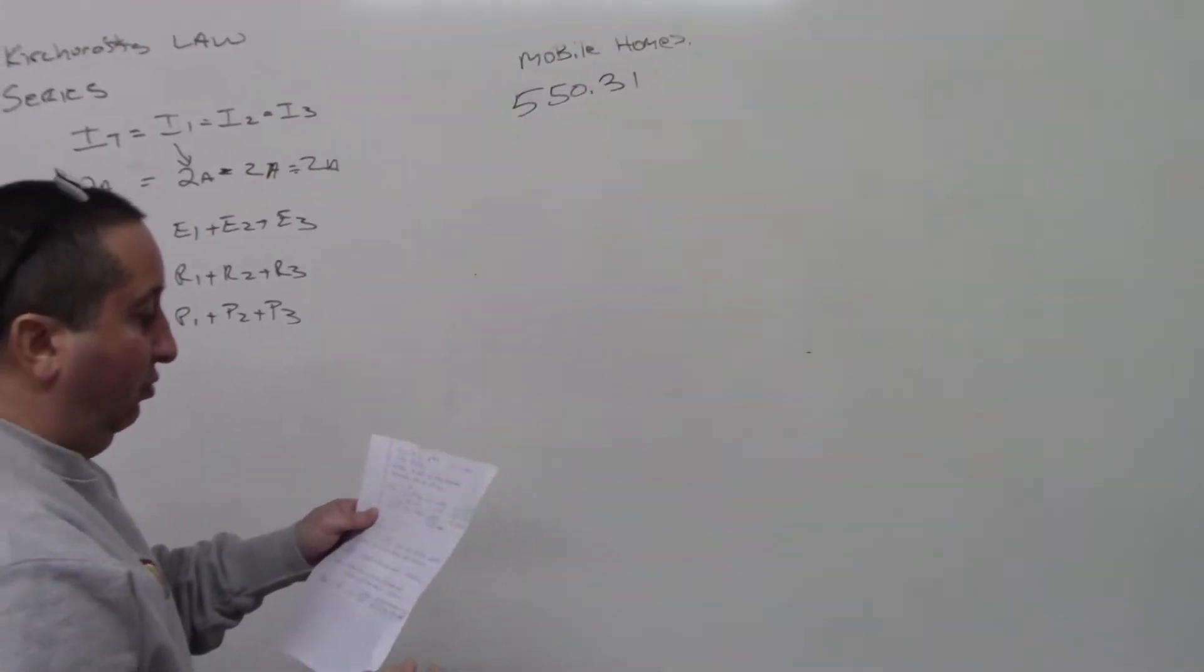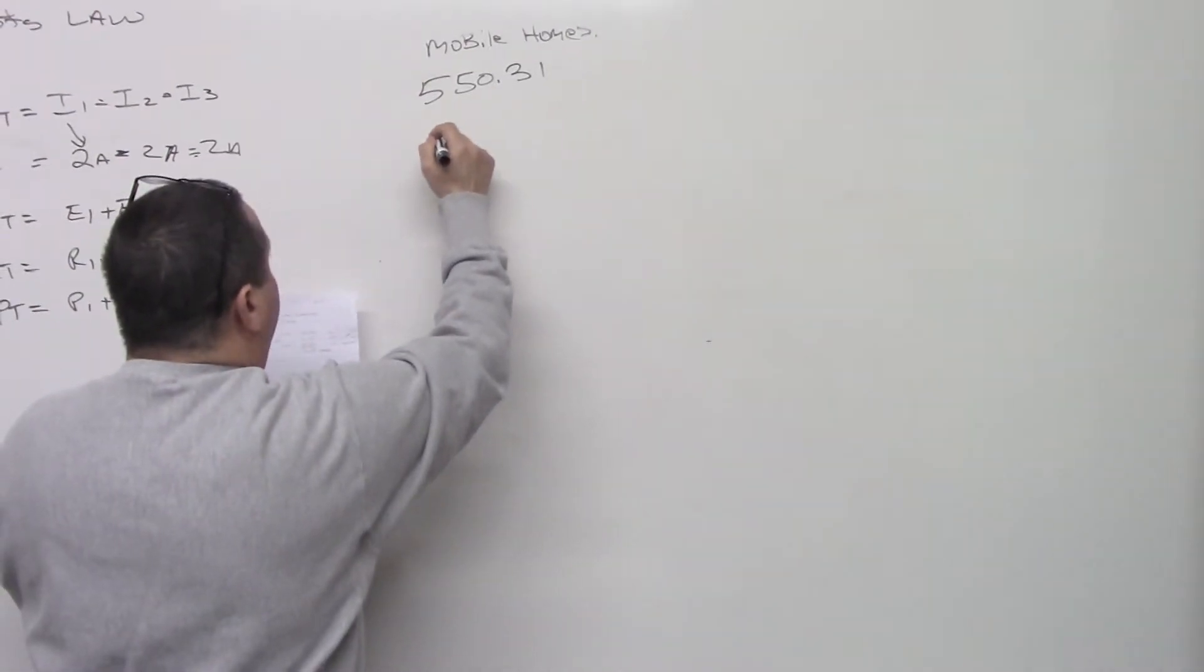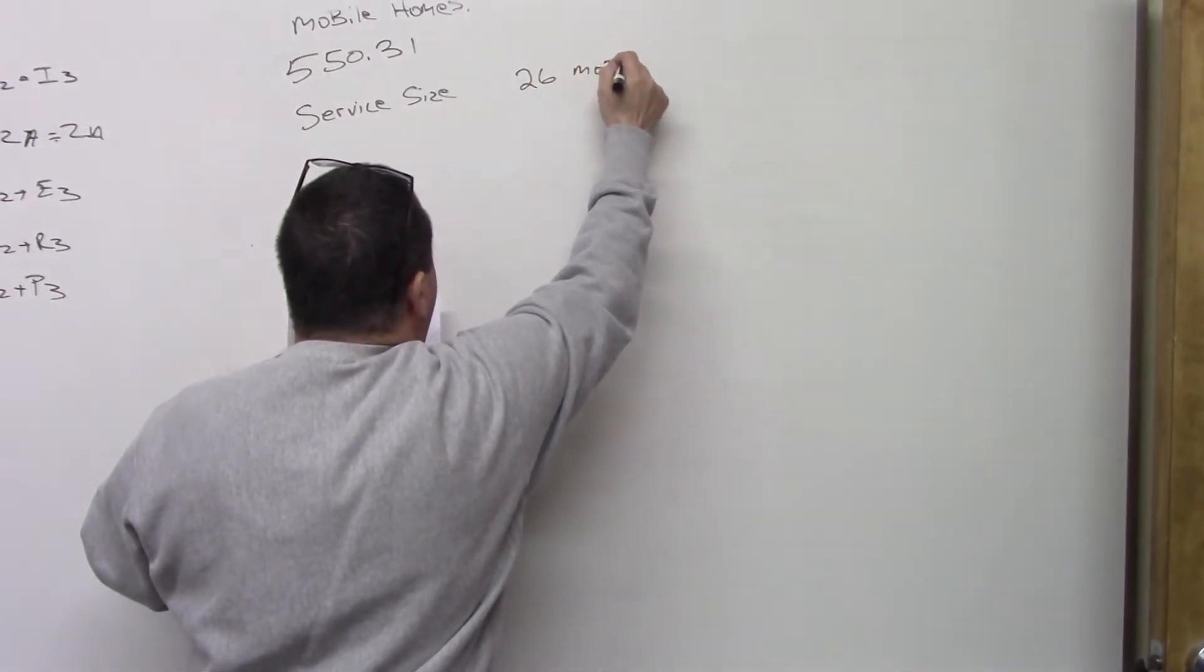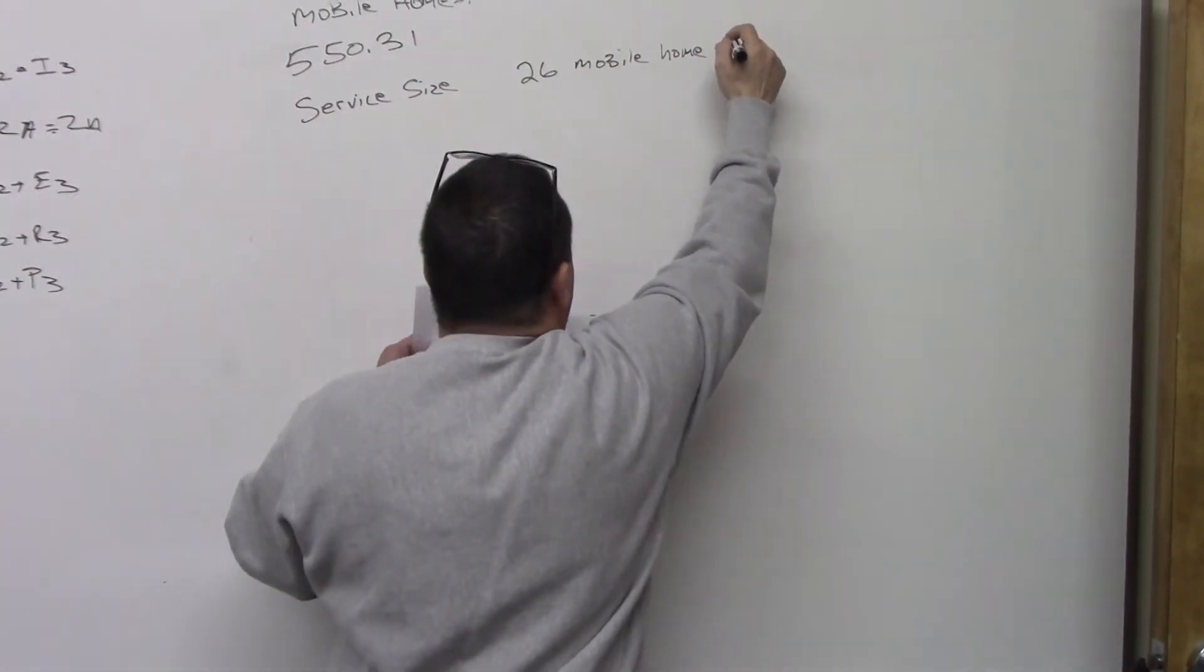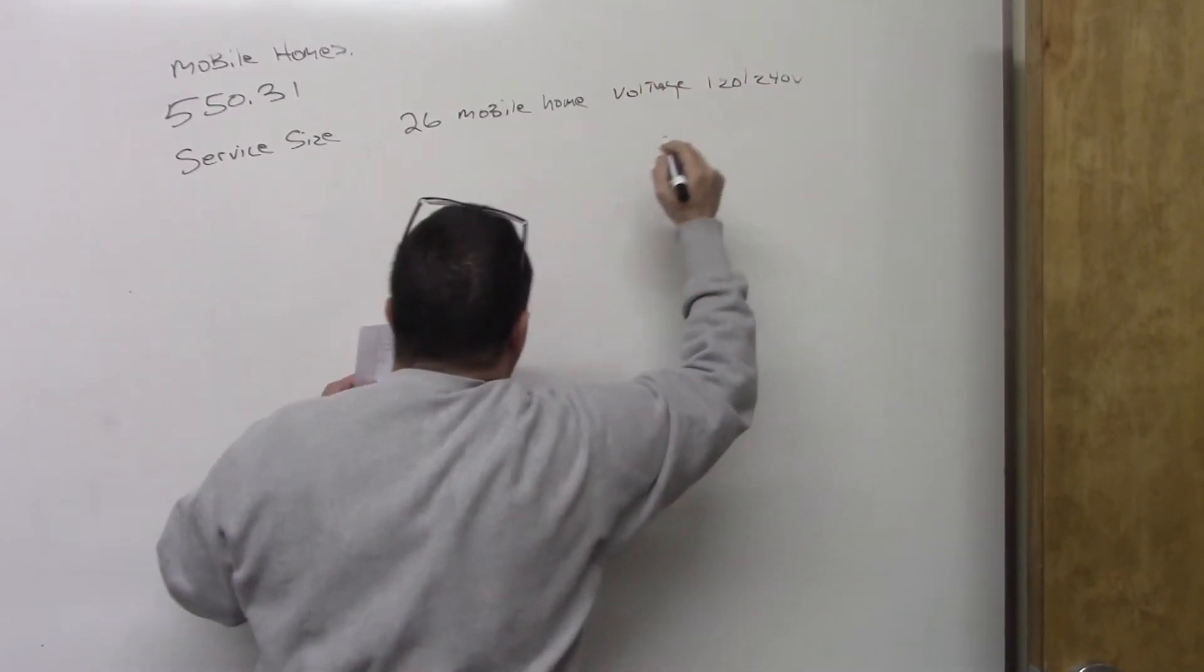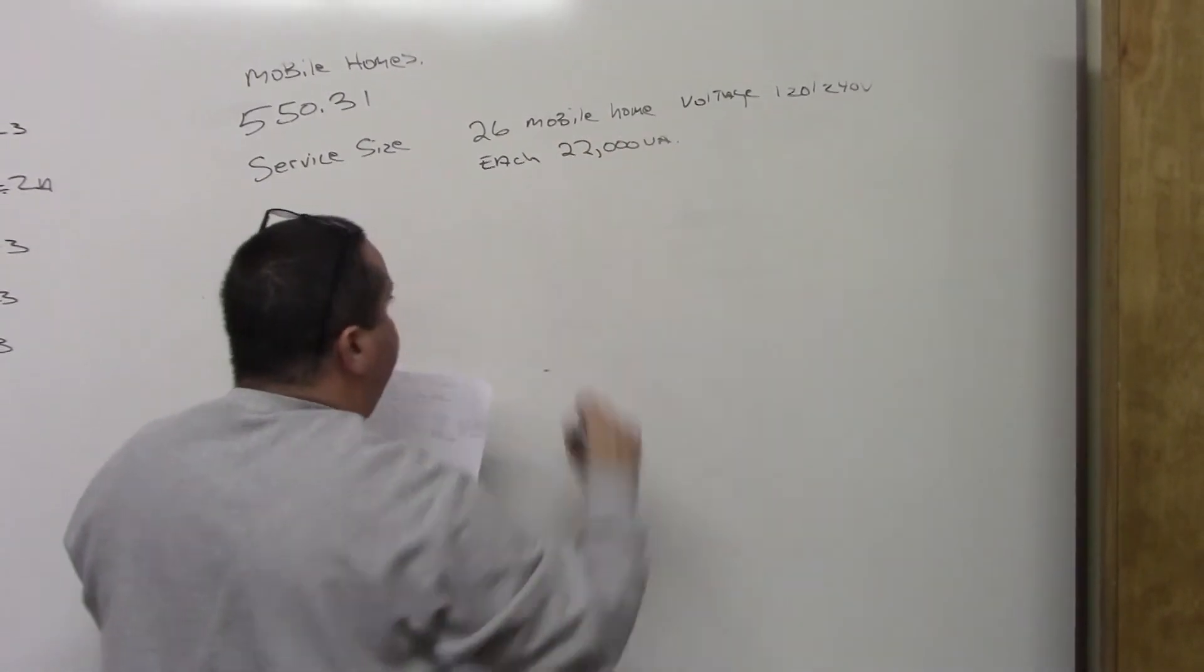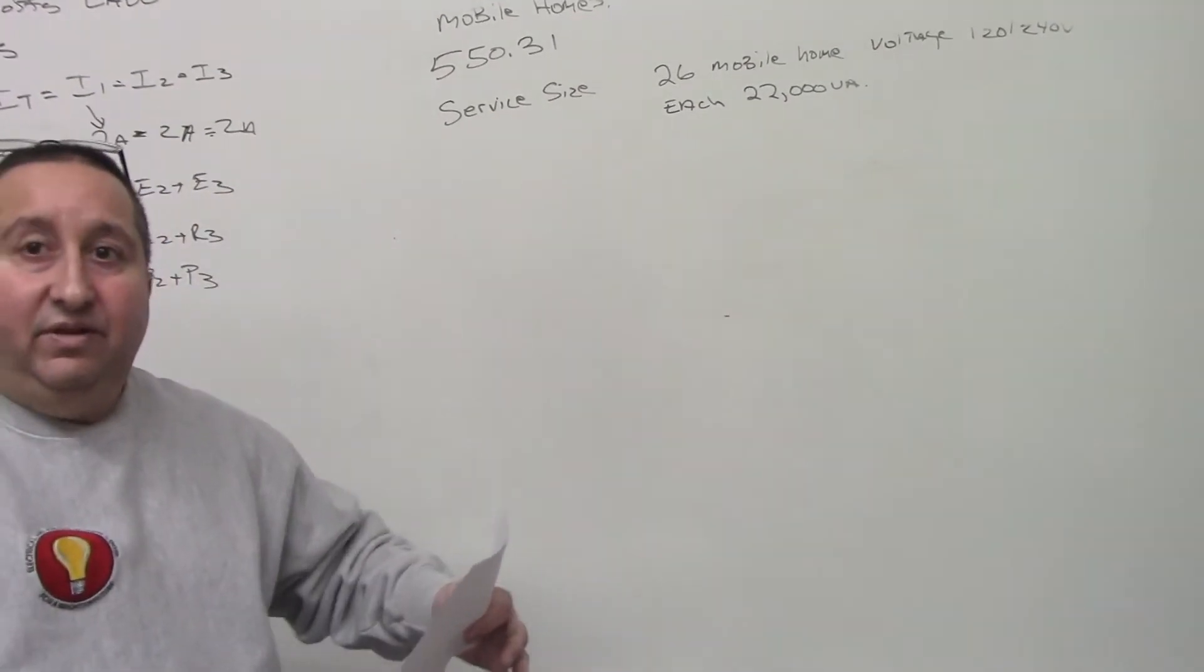So let me explain what is given and what the problem is. We want to know what the service size is for 26 mobile homes. And the voltage for this is 120/240 volts. And each home, we have a calculated load of 22,000 volt amps. So we want to find out the service conductors, the calculated load.